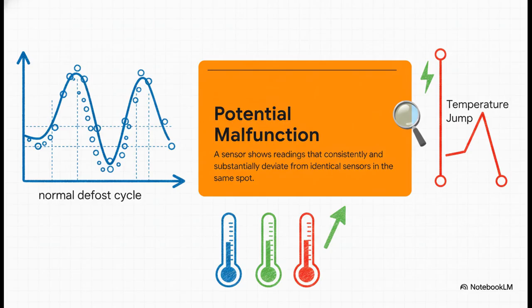So this is the most important part. A real problem looks nothing like a normal defrost cycle. Remember how a defrost cycle is a curve? It goes up gradually and comes down gradually with lots of data points along the way. A potential malfunction, which we call a temperature jump, is a massive instant change with only two data points - the reading right before the jump and the reading right after. On the graph, it looks like a straight vertical line, not a curve or a sawtooth. That's the real signal to look for.